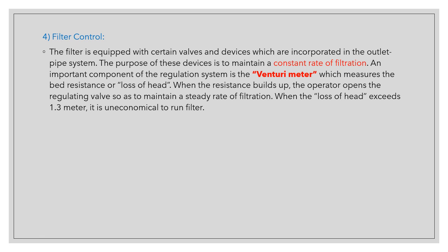Basically, what loss of head really means is how much of the sand bed has now been covered up with impurities or microorganisms and is now no longer effective. So basically it's just the resistance. And when the resistance builds up, the operator opens the regulating valve so as to maintain a steady rate of filtration. Of course, we have to open the valve more to allow more filtration to occur and provide less resistance. And when the loss of head exceeds 1.3 meters, it is uneconomical to run the filter.